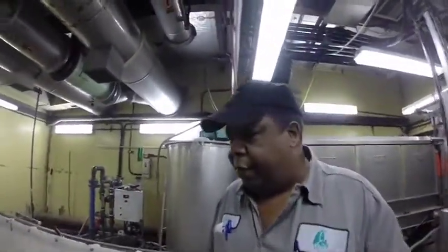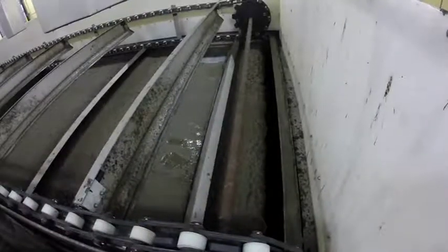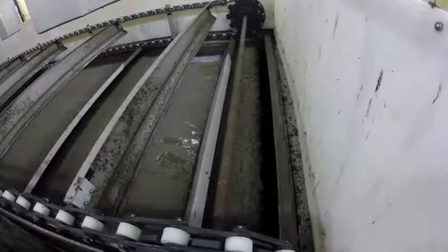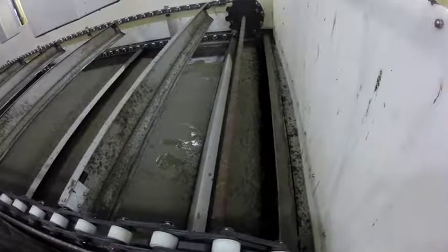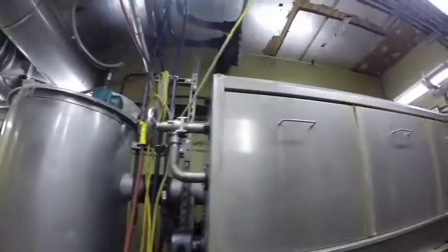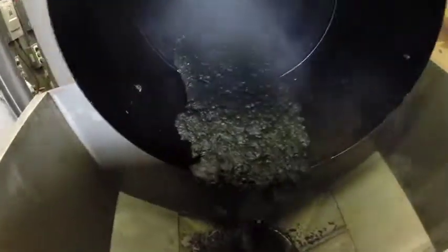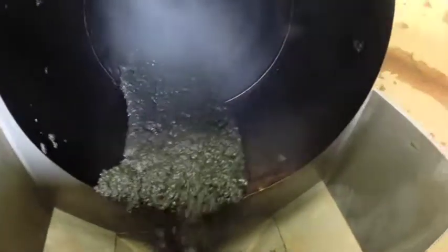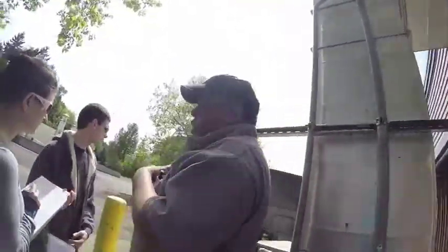So the water goes that way and the solids go that way. If the water is being recycled back through the plant again, that's what you call a waste stream, so you're adding water to your plant. This is what's called a rotary drum, turning really, really slow. I think I'm adding maybe 40 gallons a minute to this right now. Like I said, the primary digester is the one that's doing all the work.